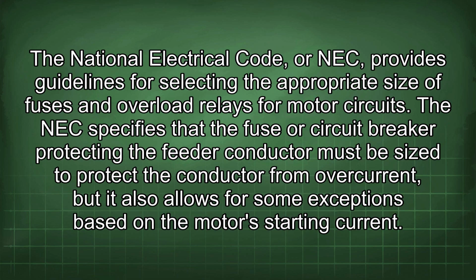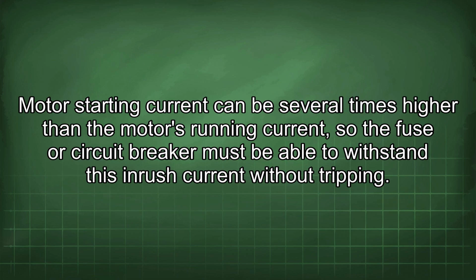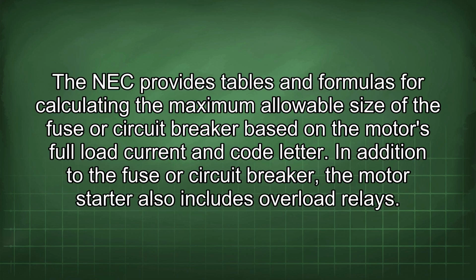The National Electrical Code, or NEC, provides guidelines for selecting the appropriate size of fuses and overload relays for motor circuits. The NEC specifies that the fuse or circuit breaker protecting the feeder conductor must be sized to protect the conductor from overcurrent, but it also allows for some exceptions based on the motor's starting current. Motor starting current can be several times higher than the motor's running current, so the fuse or circuit breaker must be able to withstand this inrush current without tripping. The NEC provides tables and formulas for calculating the maximum allowable size of the fuse or circuit breaker based on the motor's full load current and code letter. In addition to the fuse or circuit breaker, the motor starter also includes overload relays.